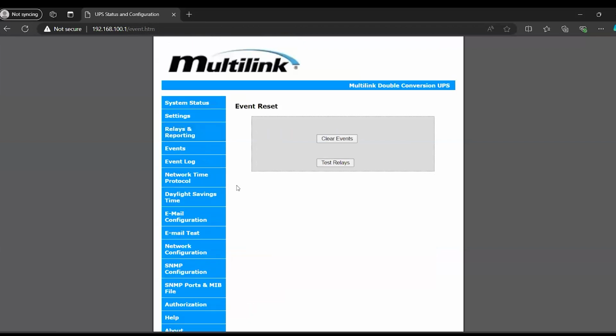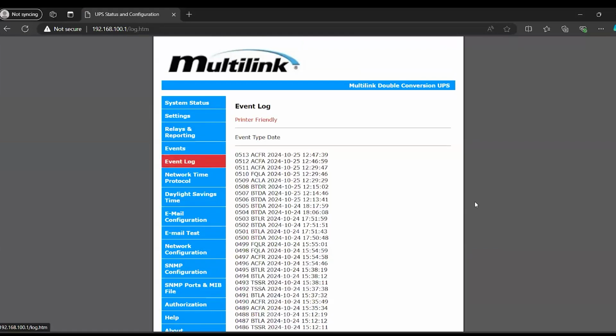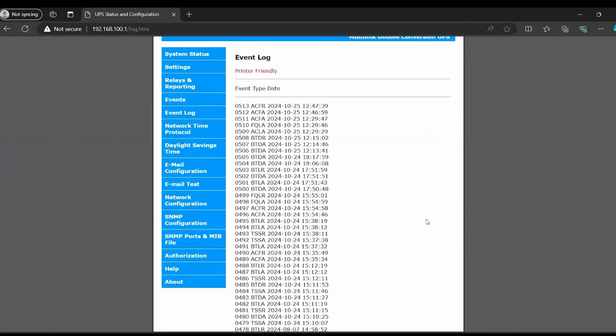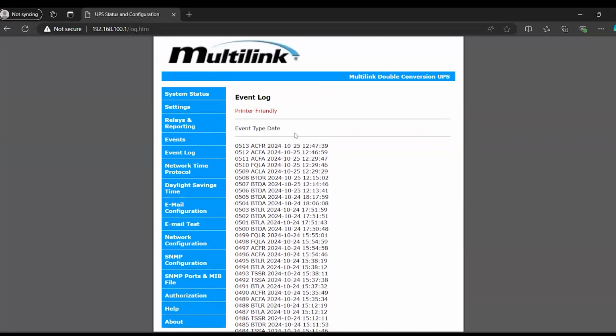Here in events is where it would show you if any events have occurred. We don't have any at the moment, so it's not showing. But if you go to the event log, it'll show you the history of the events for the UPS. You will see it shows a four-letter code, and you can reference the table in the help page for what that 4-letter code exactly means. It'll show you the date and time that event happened. And we do have an option, if you click on printer friendly up here, it'll format it into a printer friendly document. That'll make it a lot easier to print out.